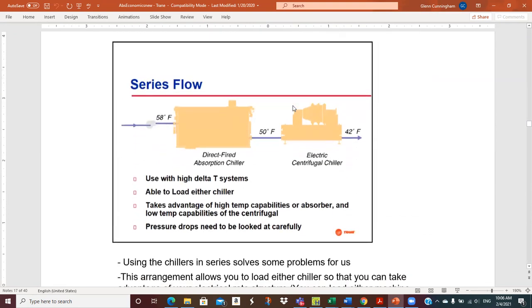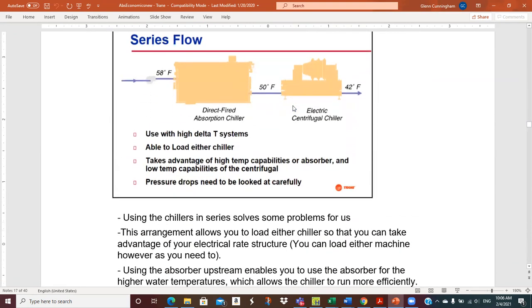And then the second one, and there's a couple of interesting notes here, but in series, and notice this, it says used with high delta T systems. Notice we got 58-degree water coming back from our building, or from our system, going out at 42. Well, 42 is pretty standard, but what is it? That's a 16-degree delta T. That's a high delta T system.